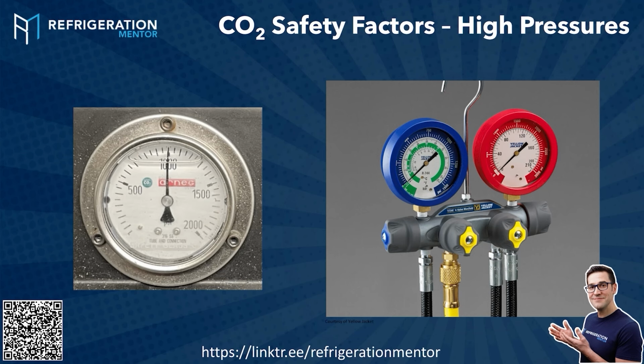Some of the safety things. When you're dealing with systems like CO2 over in the thousands of pounds, you've got to use different gauges. You can't just use your 410 gauges, even though they're higher pressure. You want to use transcritical gauges. So anytime you're on the high side, you need to use higher pressure gauges. As you can see, this goes up to 3,000 psi and 210 bar. The hoses are rated higher, where your 410 hoses are rated for 800 psi.